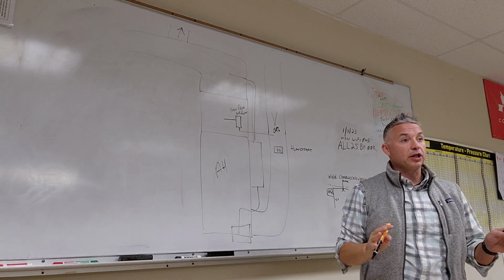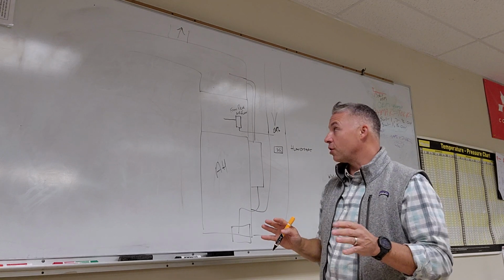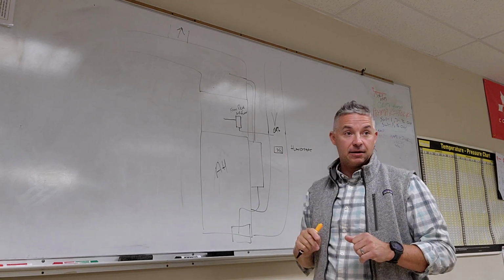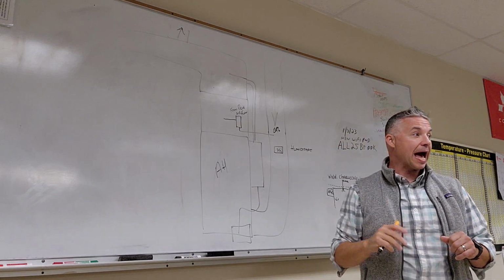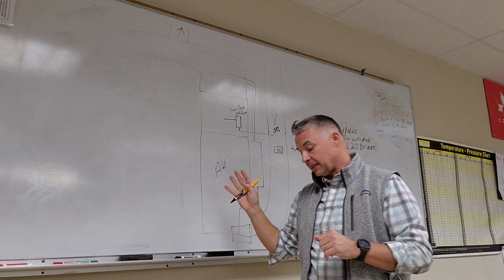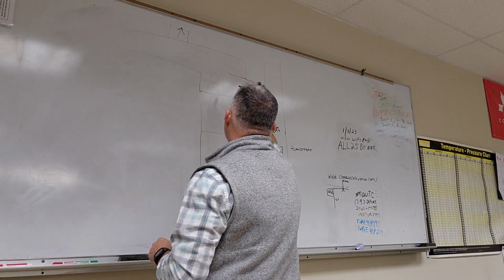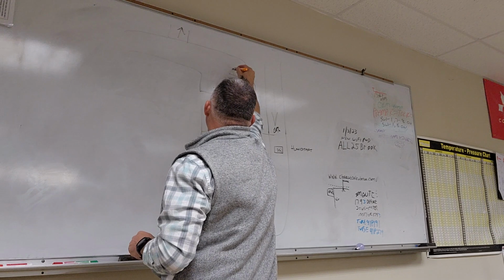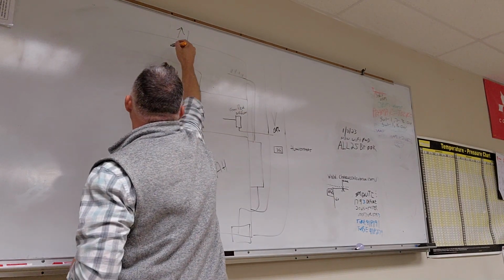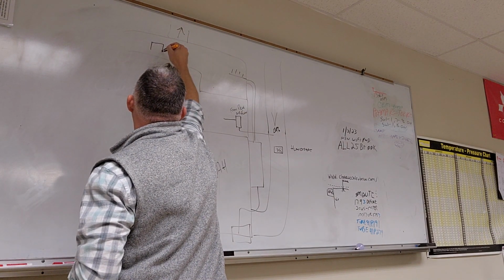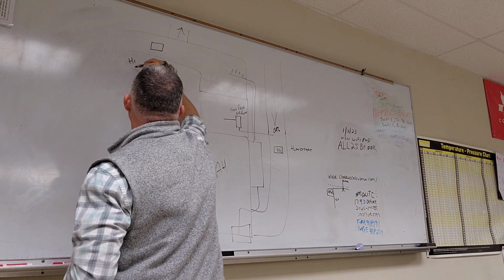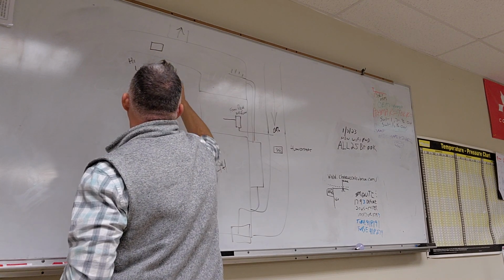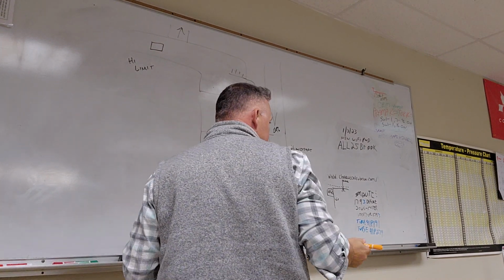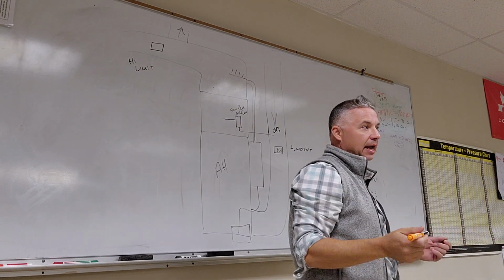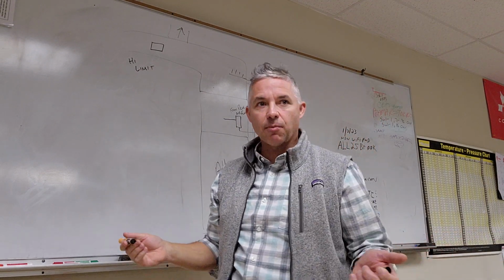Over the years of installing and operating these systems, we've also learned that we need even more than that. You need a high limit. So we put a high limit humidistat in the supply ductwork, and we put it downstream of our steam humidifier. Okay? Make sure it makes air. High limit. And a typical setting on a high limit, 80, 70, somewhere, right?